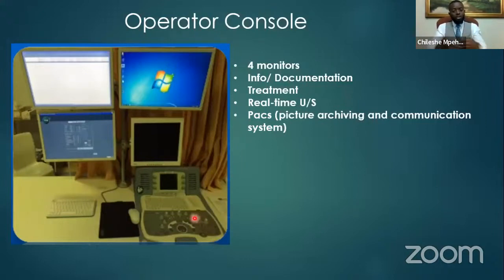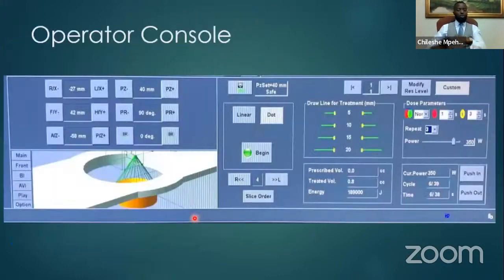Then, when we actually treat, we look at the patient's pelvis and the uterus using ultrasound. This is beneficial because the ultrasound lets us see the fibroid and the womb as we are treating, as opposed to the MRI. With an MRI guided system, you have to capture an image, and there's a lag time of between 10 to 20 seconds before you can actually treat. So you're actually treating blind, even though you had a sneak peek at what was happening. That might be problematic in certain cases, because if patients are breathing deeply, there is a certain amount of movement you can get from bowel. In that 10 to 20 seconds, you can get bowel slipping into the treatment zone, and we do not want such things to occur. It increases the risks of complications.